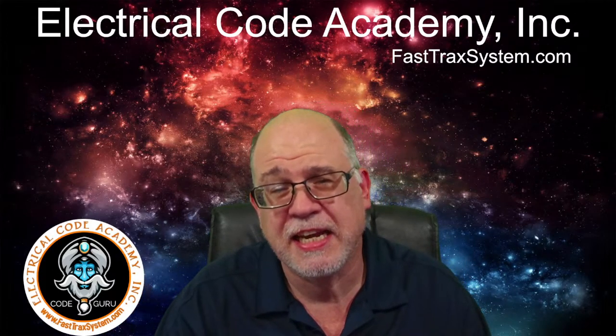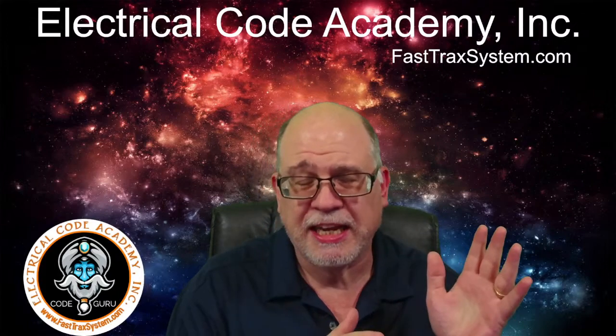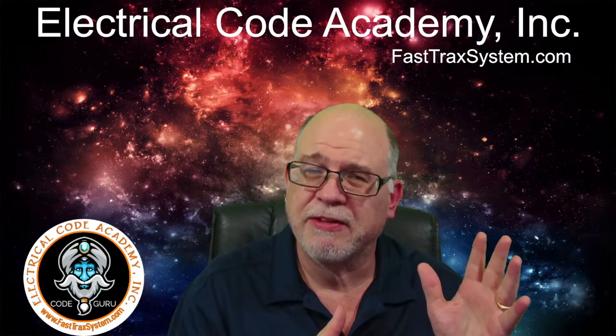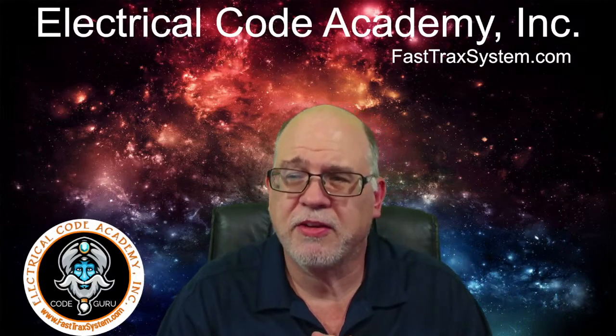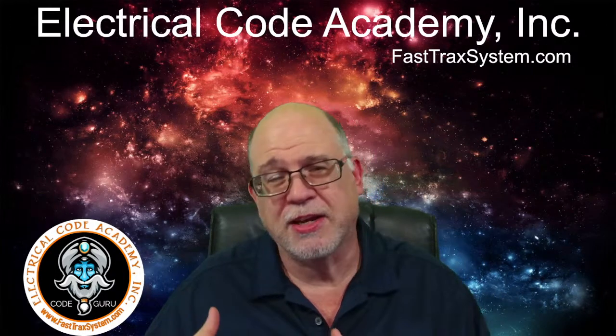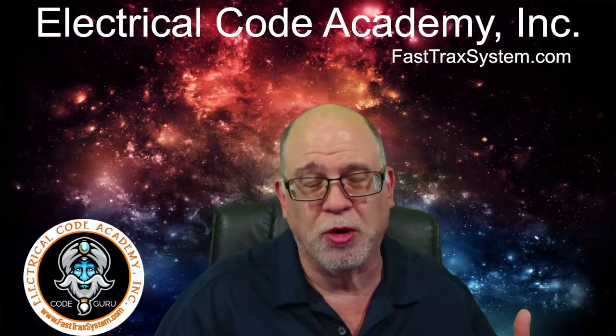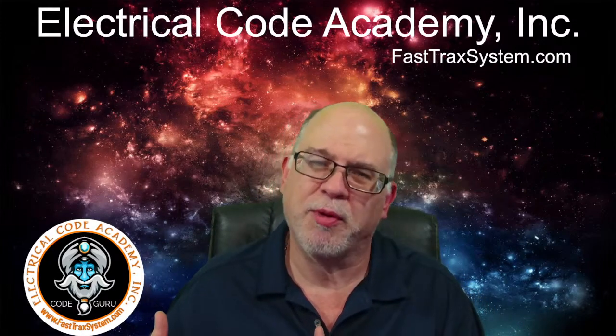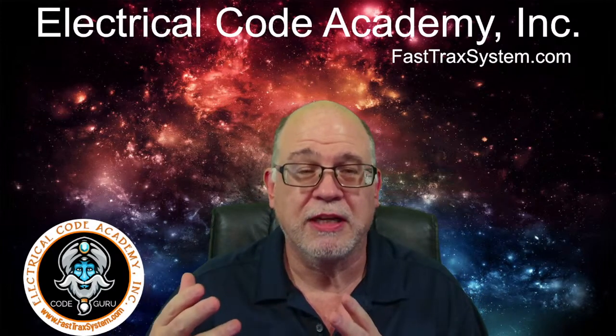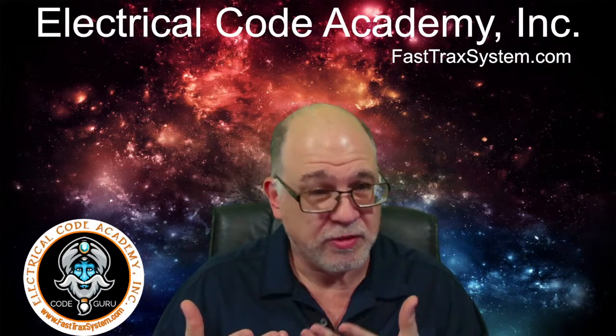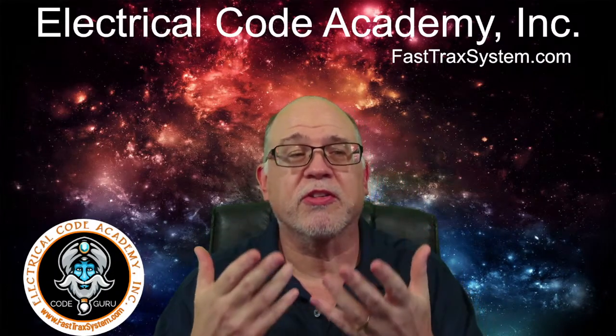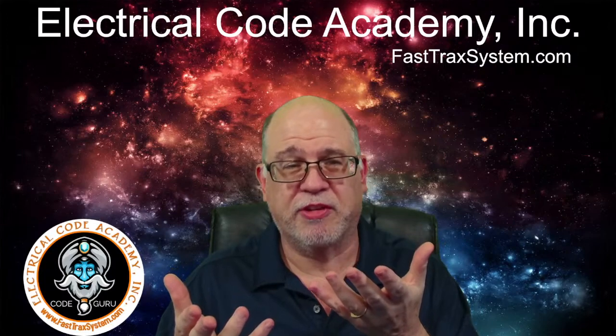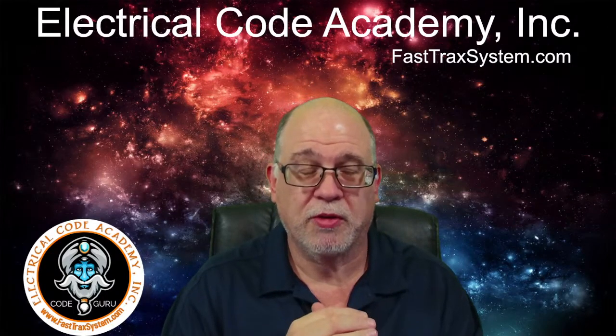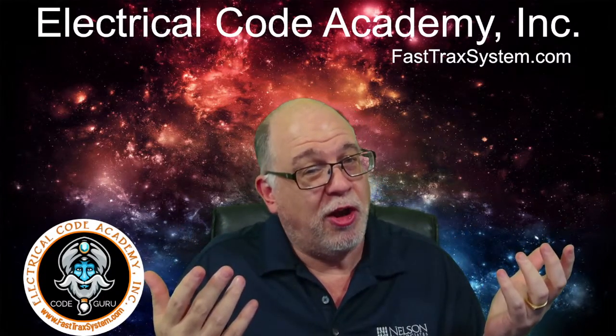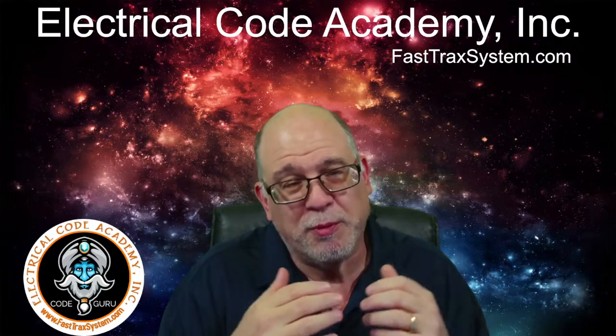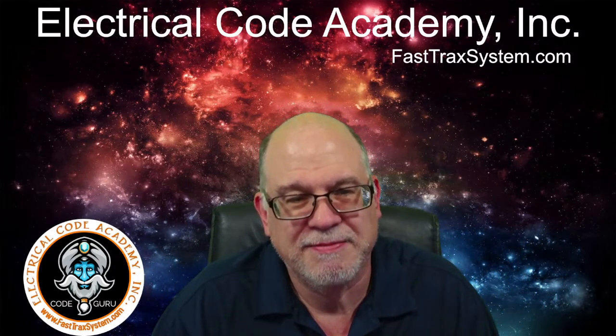The reality is you still have to know how to calculate the standard method to be able to calculate for the neutral. Why? Because in part 3, it tells you how to calculate for the neutral. It doesn't tell you how to do that in part 4, which is the optional method. So it behooves us, that's a big word for me, to understand both optional and standard. Well, since tonight wasn't going to be a night we taught, we're still going to give you a bit of a break. We're going to do the optional method tonight.